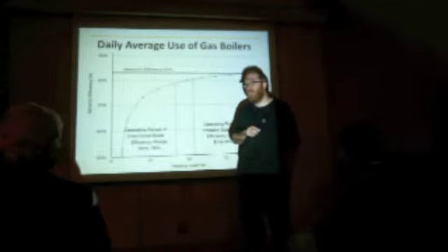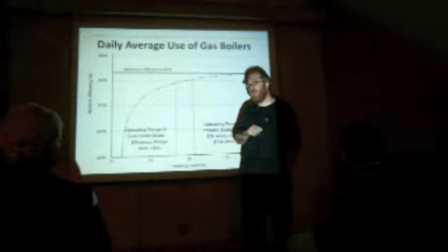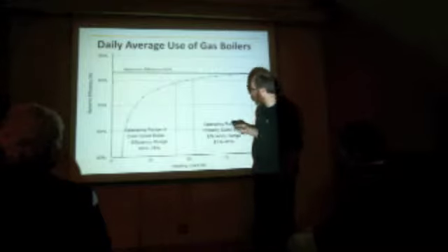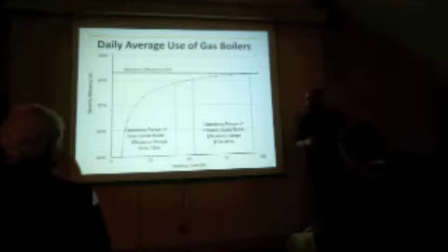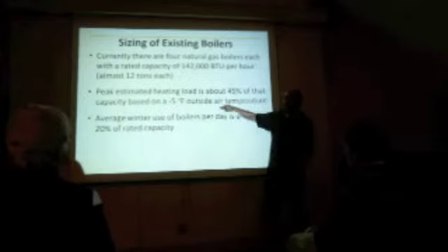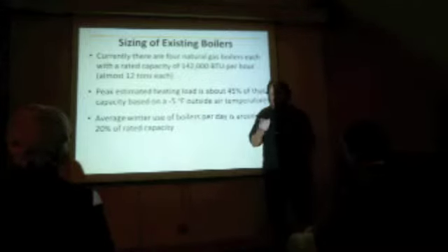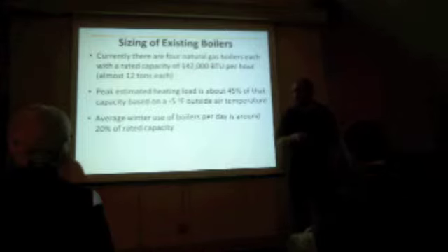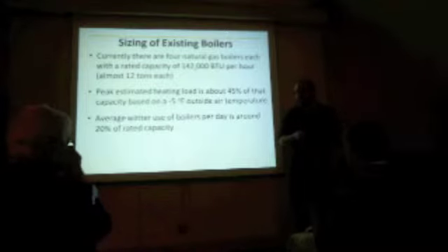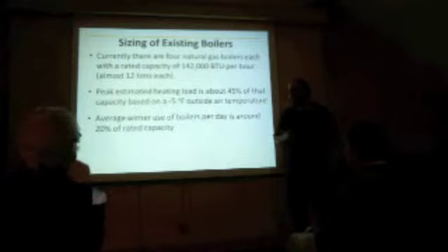If I'm understanding your graph, not coming all the way to even 50%, does that mean that at the coldest day there's still only 2 boilers working? We'd have to know more about how your system is controlled, and that would be one of the recommendations that I'll make. Even on the coldest day that we're designing the system for, we should only expect 2 of those boilers to actually be active. But when we looked downstairs, all 4 boilers are hot, even today. Yeah, and so it would be more efficient to have maybe 4 boilers, but all of them be smaller. Or to stage them and only bring them online as the capacity is needed.